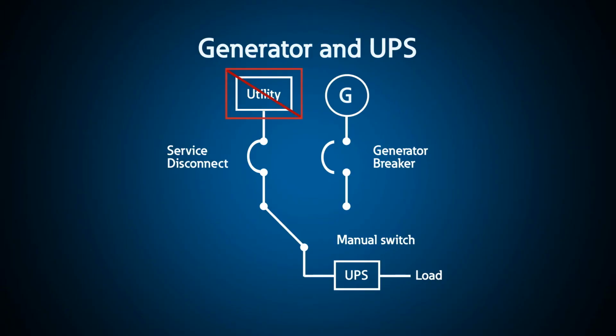Why would you want both a generator and a UPS? This is a good question, and the answer is that the generator will not start fast enough to prevent the electronic equipment from losing power. If you have both, then while the UPS is providing power immediately after the outage, you will have enough time to connect the generator safely.